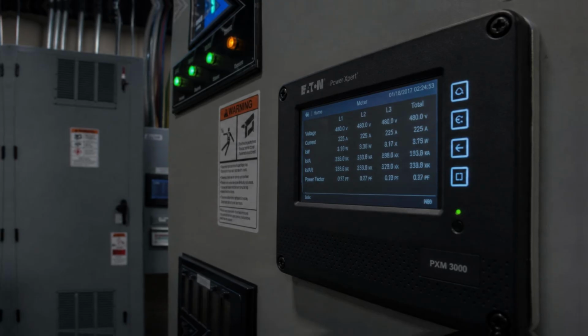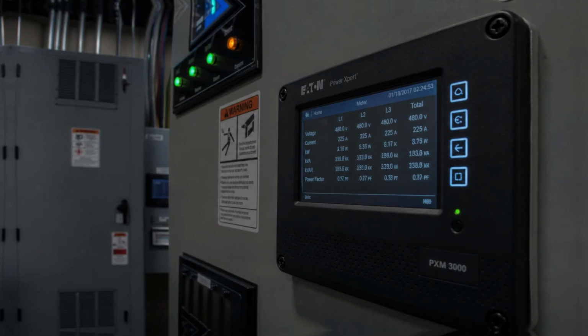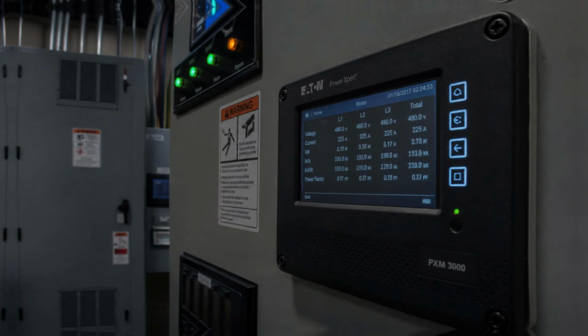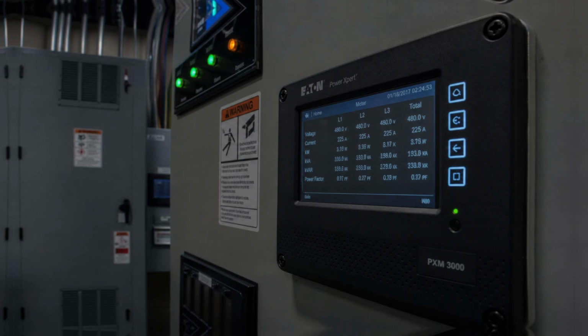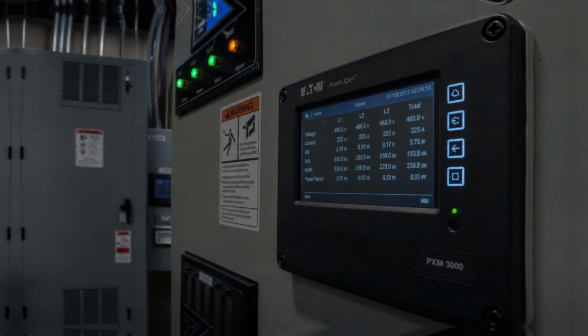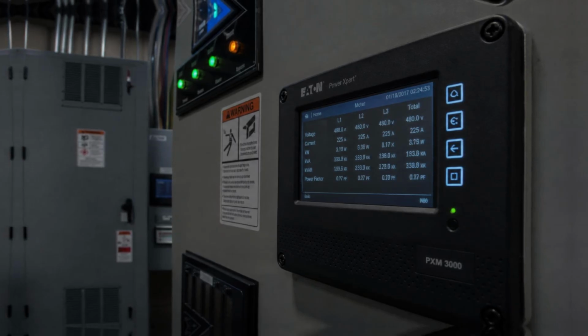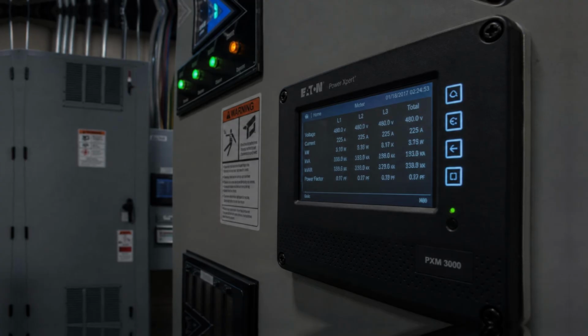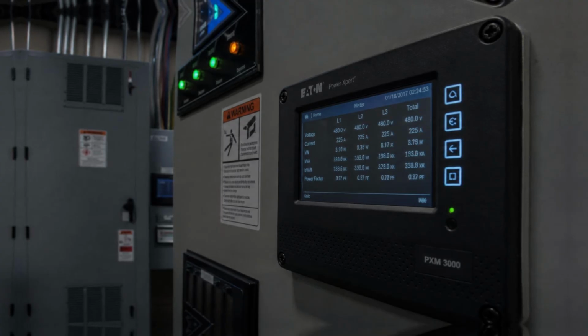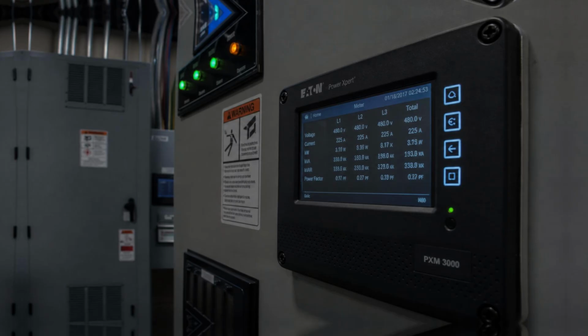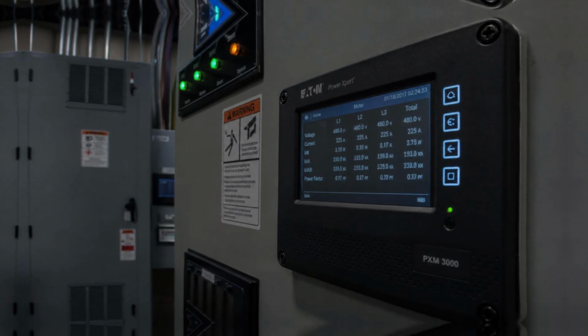But an emergency power system introduces a second source, a backup, an alternative that stands ready to supply the building's most critical loads if the first source ever fails. And the moment that first source fails, or rather, the moment the monitoring system decides it has failed, a decision must be made. Which source should be feeding these loads right now? That decision and the physical act of carrying it out belongs to the automatic transfer switch.